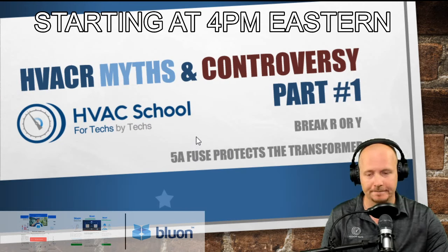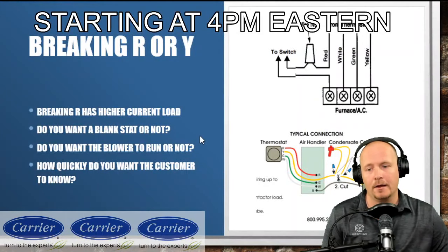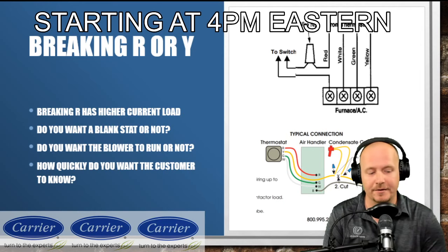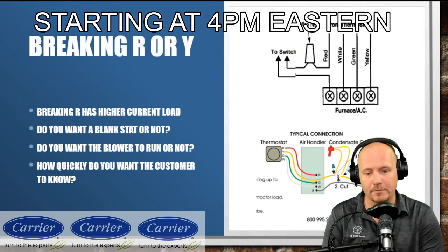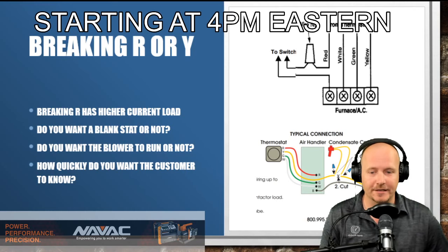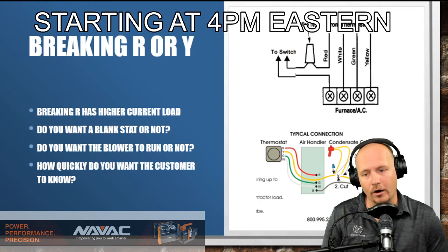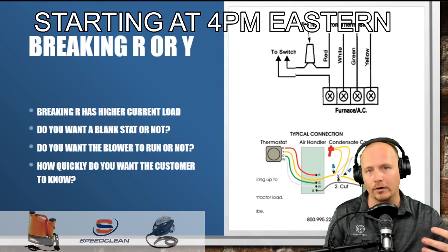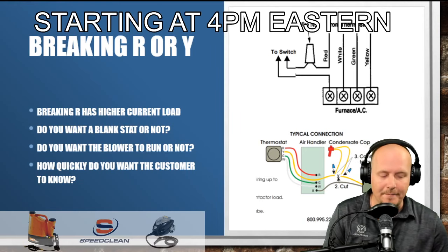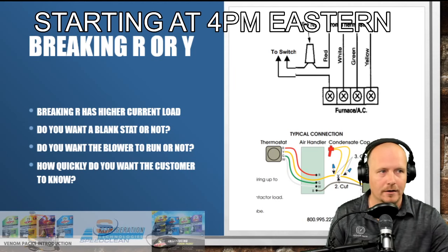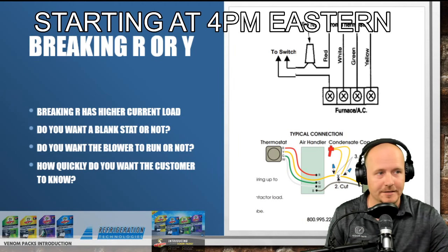So first thing. Do we break R or Y? That is the controversy, and you do have some different opinions about whether to break R or Y out there. So here's the first thing to consider that maybe you haven't considered, and that is that when you break R, you have a higher current load. So you're breaking more current. And does that matter? Well, we'll talk a little bit in a second about why that might potentially matter, or it may not. Depends on the application.